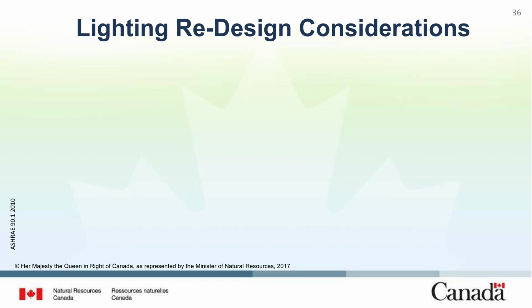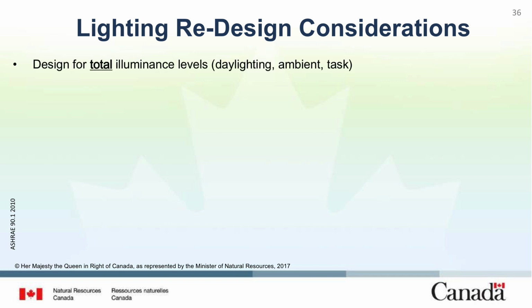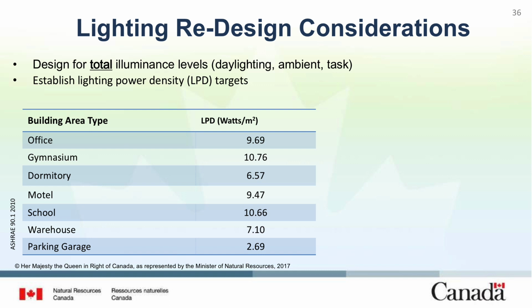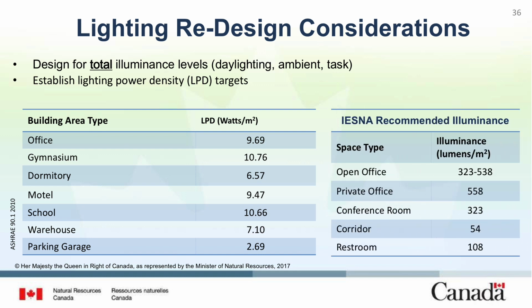The lighting redesign requires consideration. What the designer needs to do is find the appropriate illuminance levels for a space and then set the lighting power density to achieve those levels most efficiently. The lighting power density is the watts per square meter that we want to achieve for that space. Both the illuminance and the lighting power density should be considered upper limits.